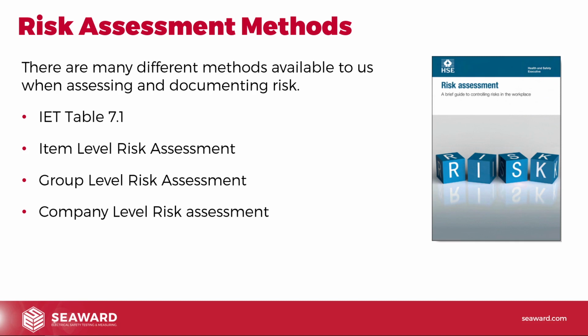Now, the reason that they're not very good risk assessments that way round is because they're not based on risk. A lot of the time these things are based on convenience. It's convenient to test everything in the school in the summer holidays. So we'll set a policy that we do all the PAT testing in the school in the summer holidays, and even the high risk items and the low risk items, we don't treat them any differently. We just do everything at that time. So really, calling it a risk assessment is probably wrong, because a lot of these things aren't actually based on risk, they're based on convenience.